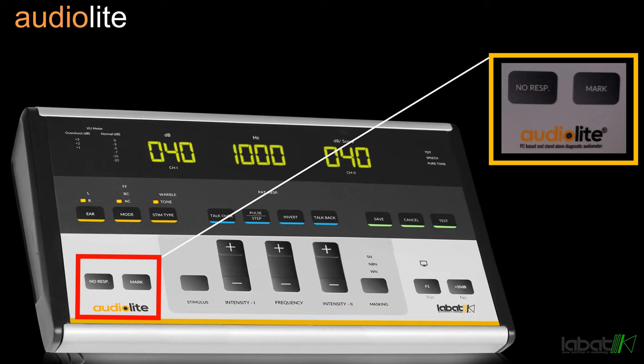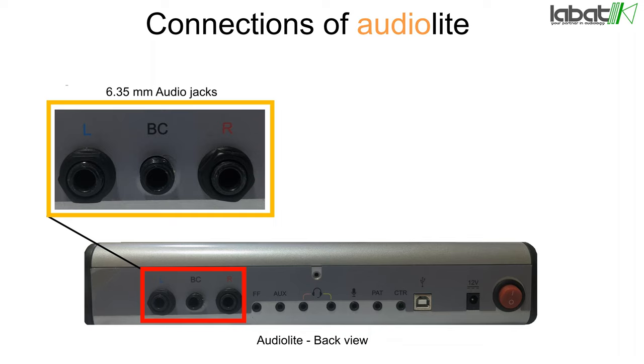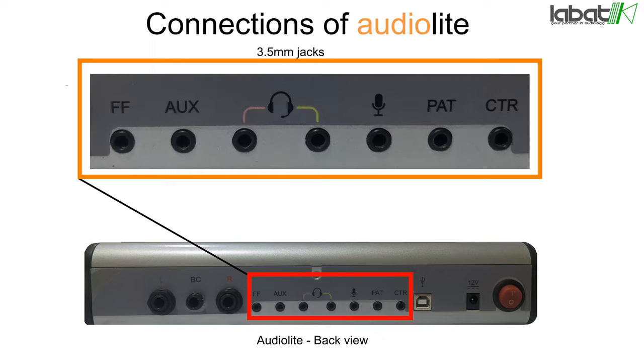L and R jack is used to connect the headphones. BC jack is used to connect the bone conduction transducer. FF jack is used to connect the free field speakers. AUX jack is used for auxiliary external input, like pre-recorded words.